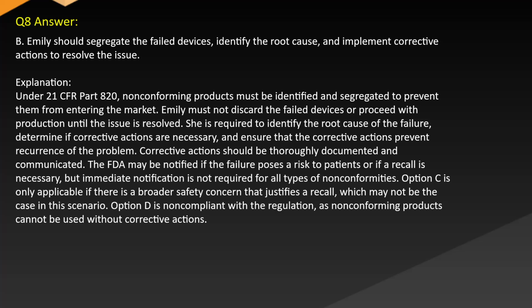Answer: B. Emily should segregate the failed devices, identify the root cause, and implement corrective actions to resolve the issue. Explanation: under 21 CFR Part 820, non-conforming products must be identified and segregated to prevent them from entering the market. Emily must not discard the failed devices or proceed with production until the issue is resolved. She is required to identify the root cause of the failure, determine if corrective actions are necessary, and ensure that the corrective actions prevent recurrence of the problem.